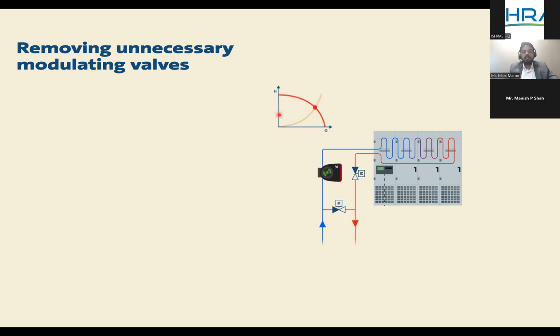And let's say in a conventional system, this control curve will always stay somewhere at 20 or 30% of the overall head. So that static will always be there. We cannot further modulate the pump below that static. It has to be there in the system, and the control curve follows that static, based on the static head which we have to maintain. And that is the friction which the valves are creating, which the valves are always putting into the system, and that head is added as pump head into the pump.